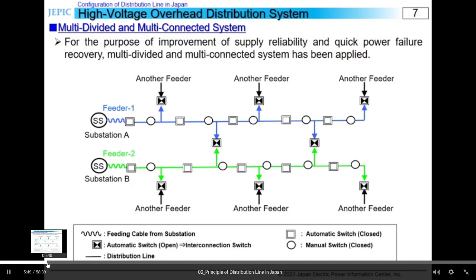of high voltage overhead distribution system in Japan. For the purpose of improvement of supply reliability and quick power failure recovery, multi-divided, multi-connected system is popular in the configuration of 6.6 kV distribution system. One distribution line is divided into several sections, and each section is connected to its neighboring feeder so that each section can be energized each other.